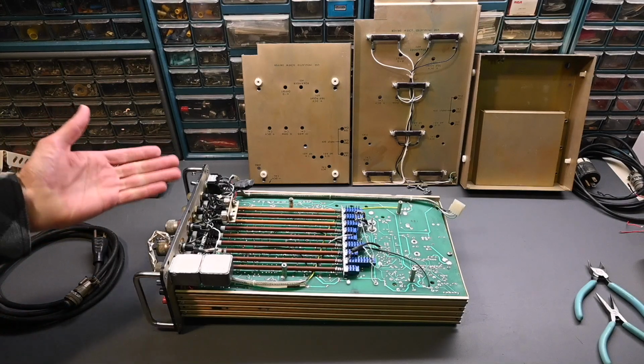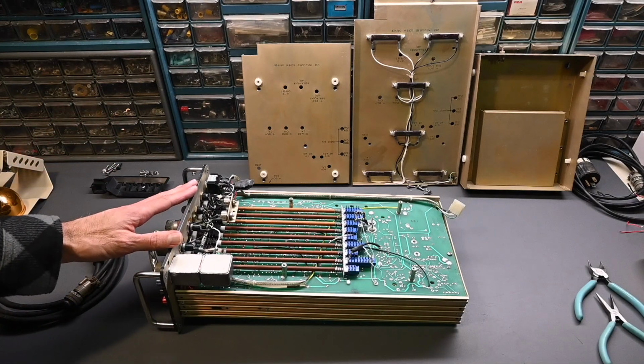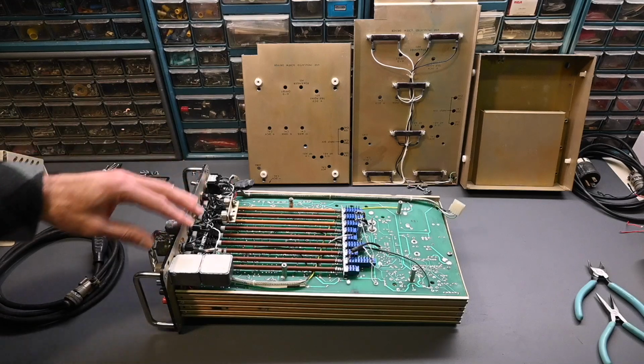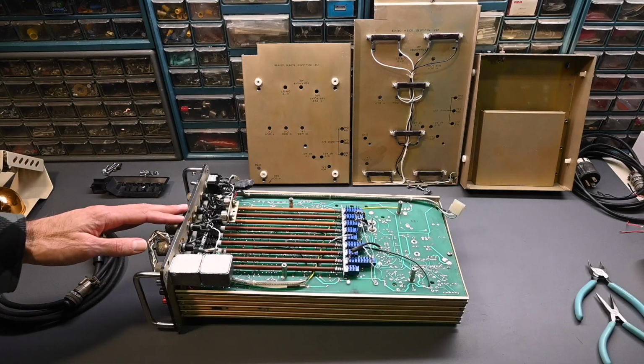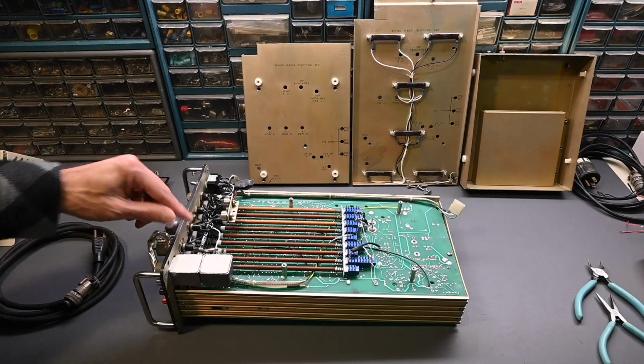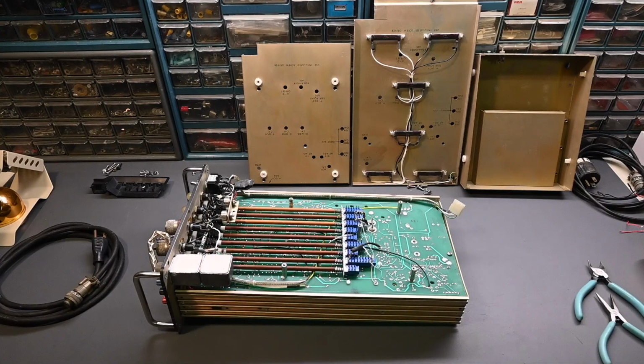I actually think this whole front panel needs to be removed because the rubber piece around the buttons that makes them waterproof is not installed correctly, so that needs attention. It doesn't look torn, but it's not installed correctly. There's a second piece of metal that clamps it in place, and it's not in position.